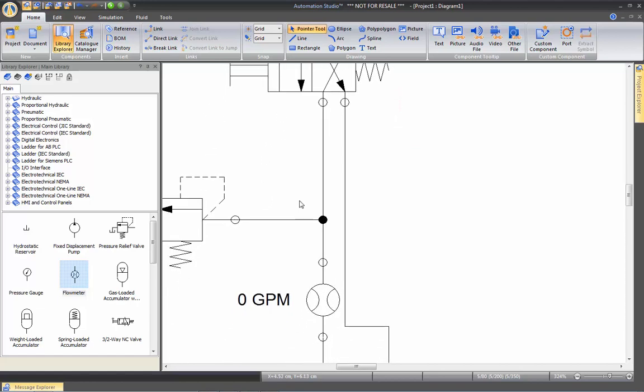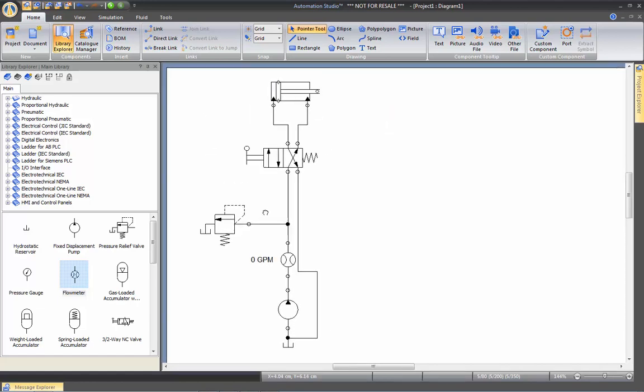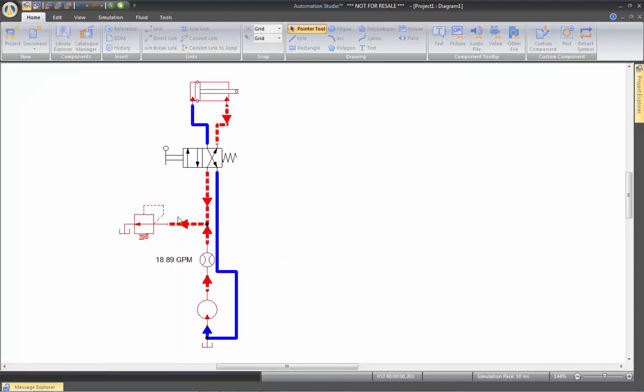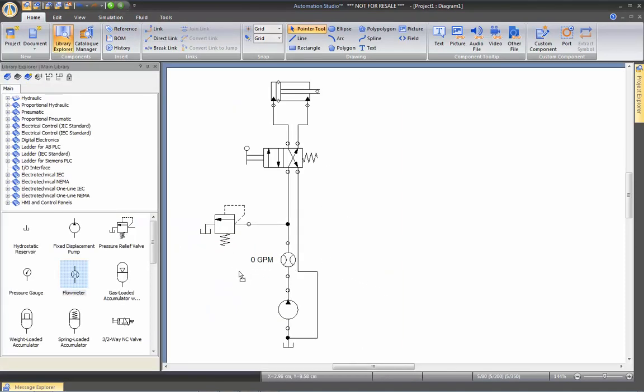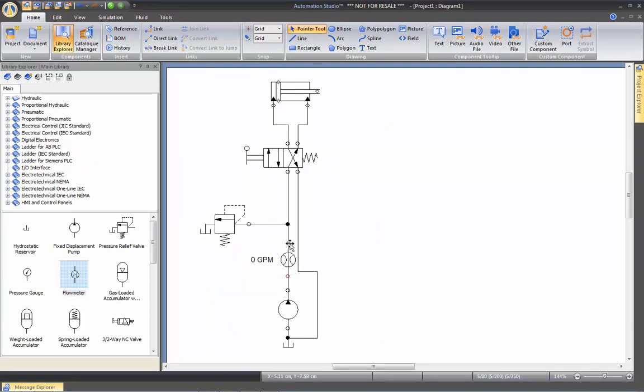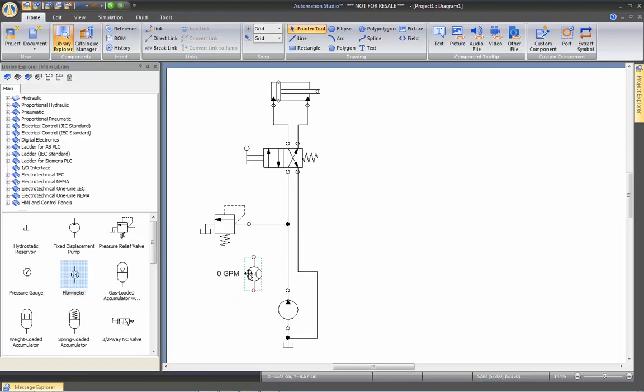Something important to notice also in simulation is that if I simulate now, you see that all the lines are never going through any symbols. If you have a schematic which you see a line going through a component, this means it's not well connected. Let me show you an example. You see that the flow meter now is well connected. And if, for example, I would have brought it like that without holding the shift down, you see the dots are red. If I launch a simulation, you see it's going right through the component. This is a good indication that something is wrong with your drawing. So let's put it back correctly. I'll hold the shift down and drag it in there.